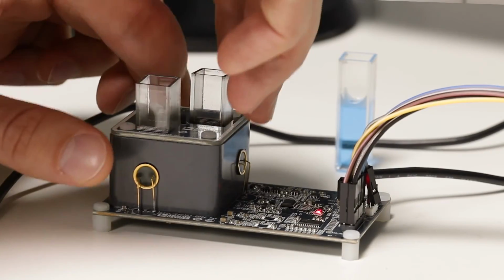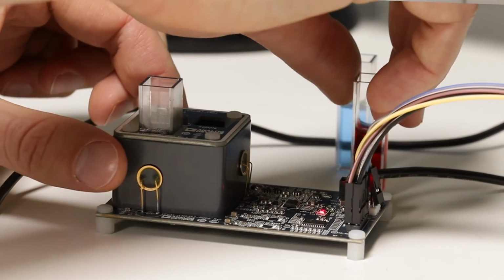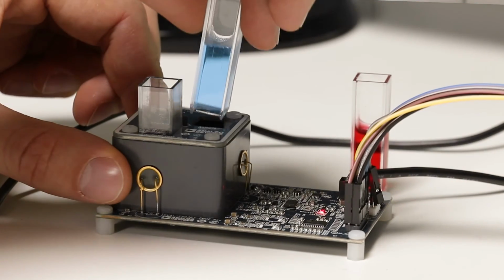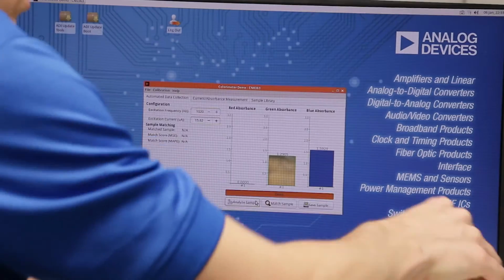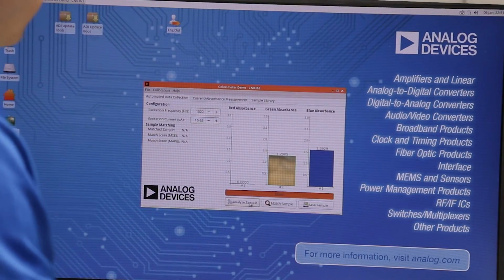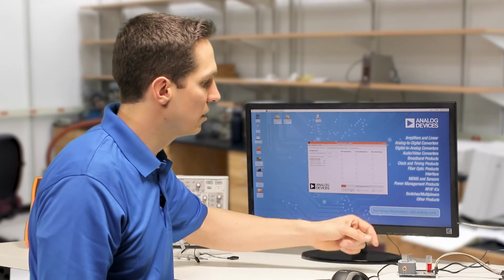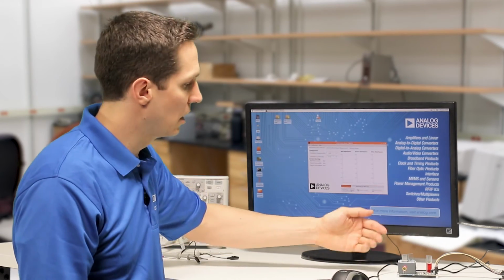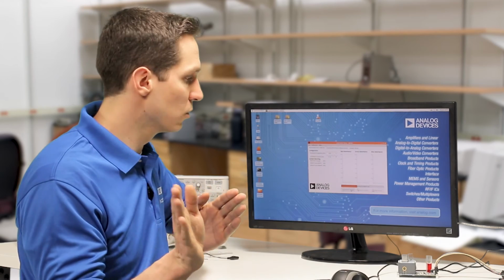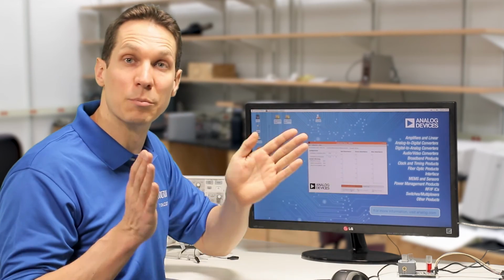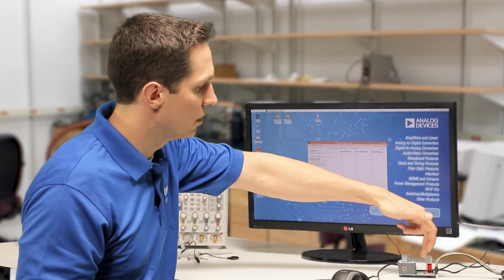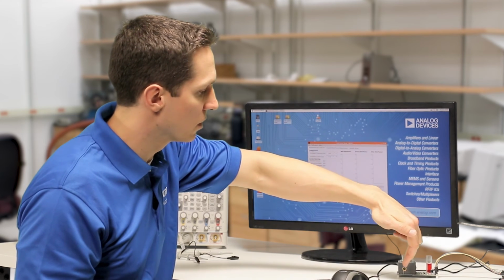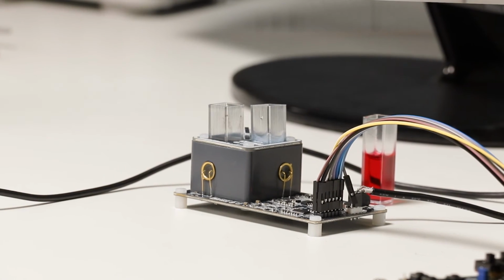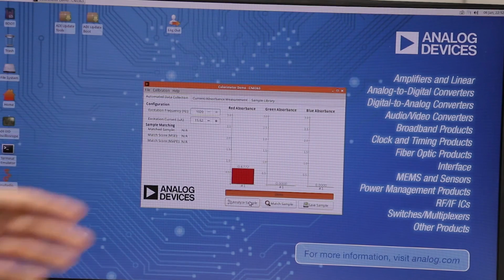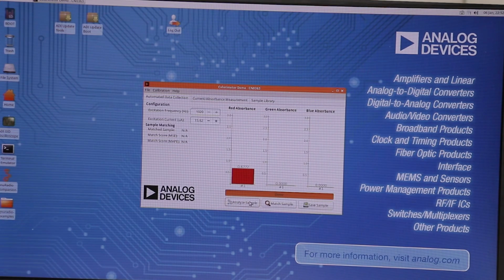So we can take this out and transfer a red sample, switch it out for a blue sample, and run it again. And again, what it's doing is it is lighting up these lights, putting it through a beam splitter, running the light through distilled water and also through the sample, and then comparing the absorbance with these two sensors over here. And we'll see on here that we should get some red absorbance. Yep, so we get 0.6772.